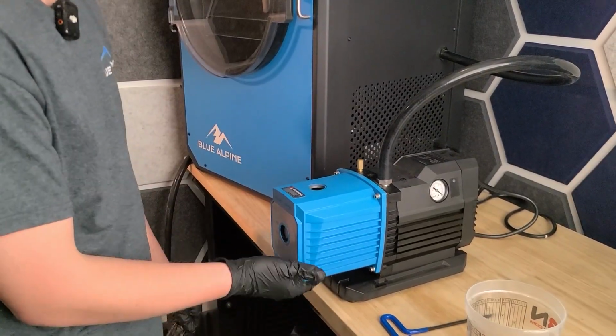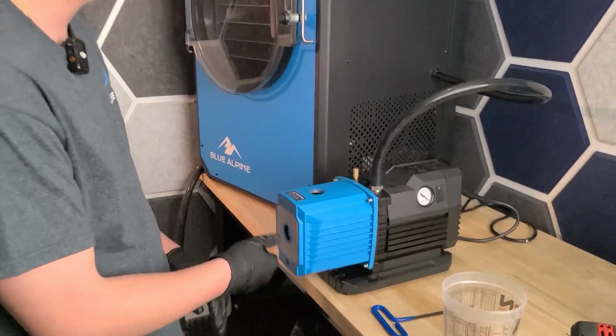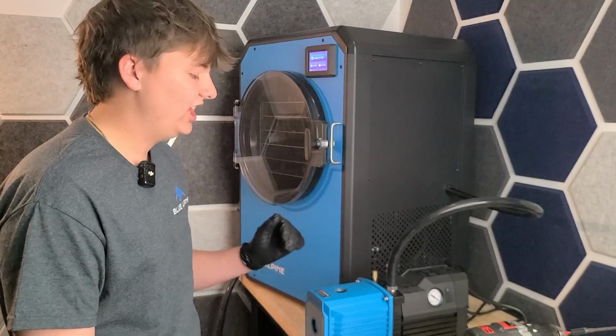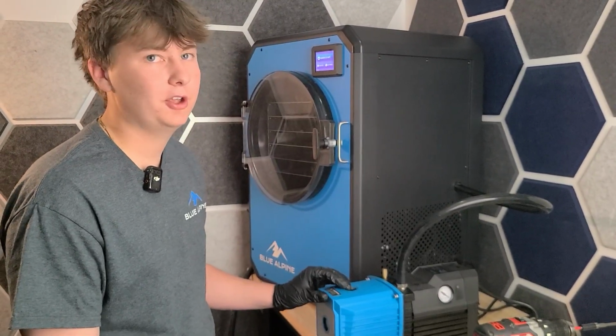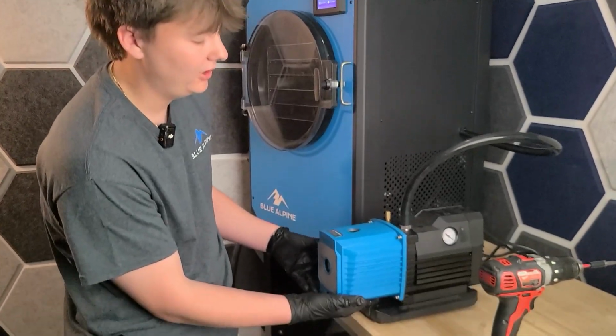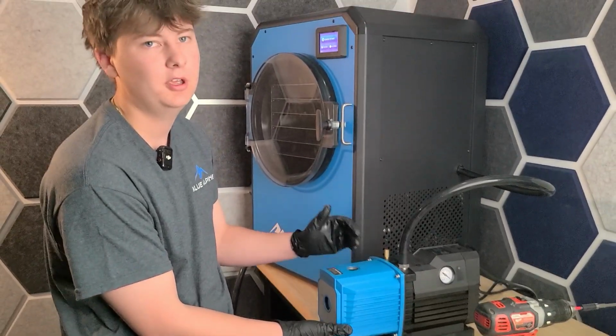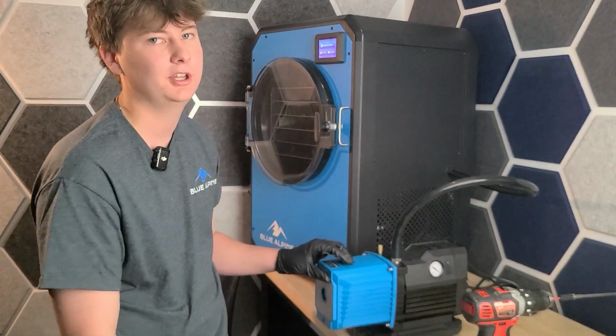We have already drained the oil out of this vacuum pump just to keep things clean for the video, but your vacuum pump will need to be drained. Keep in mind that when you do take apart your vacuum pump, there is going to be more oil sitting at the bottom of your container and through each stage of the vacuum pump. So just be cautious to have paper towels on hand when taking your vacuum pump apart.